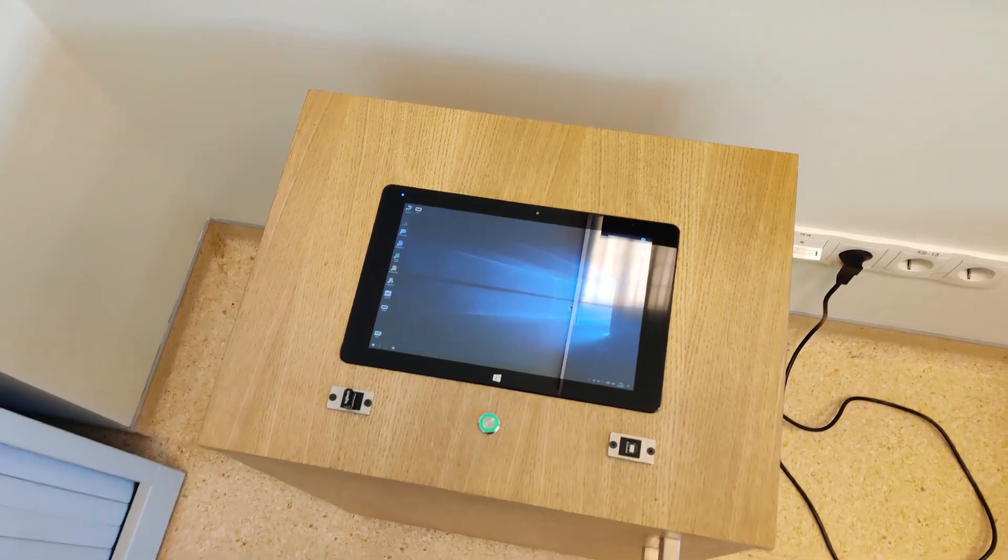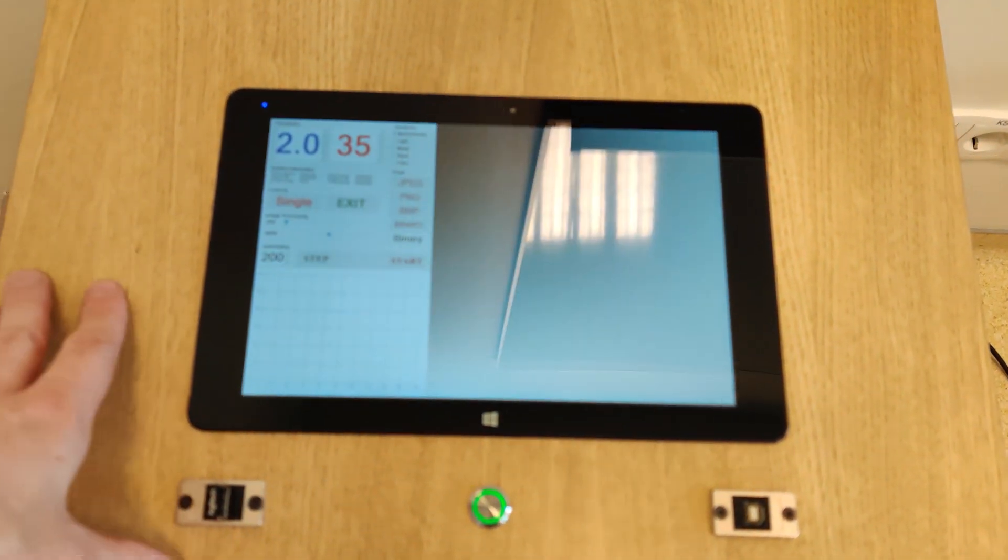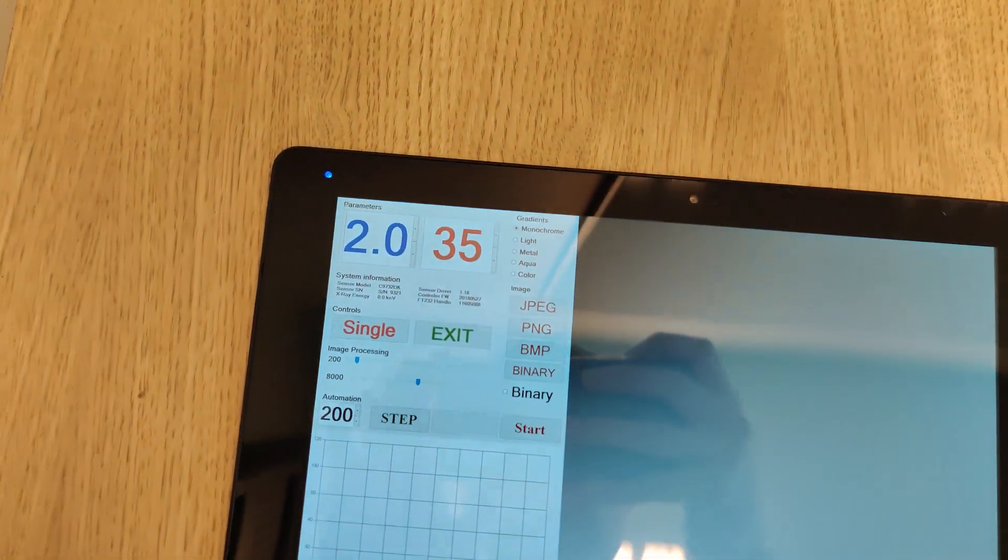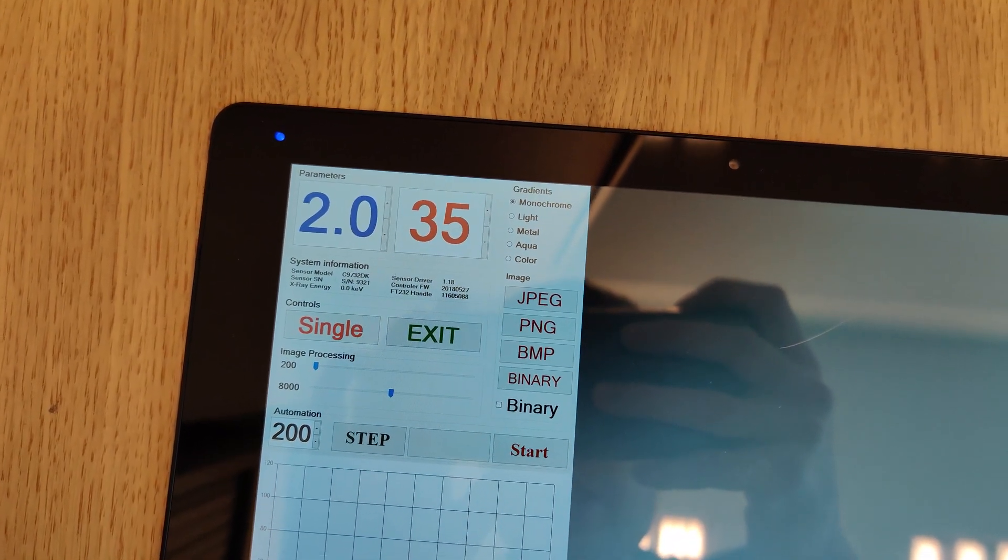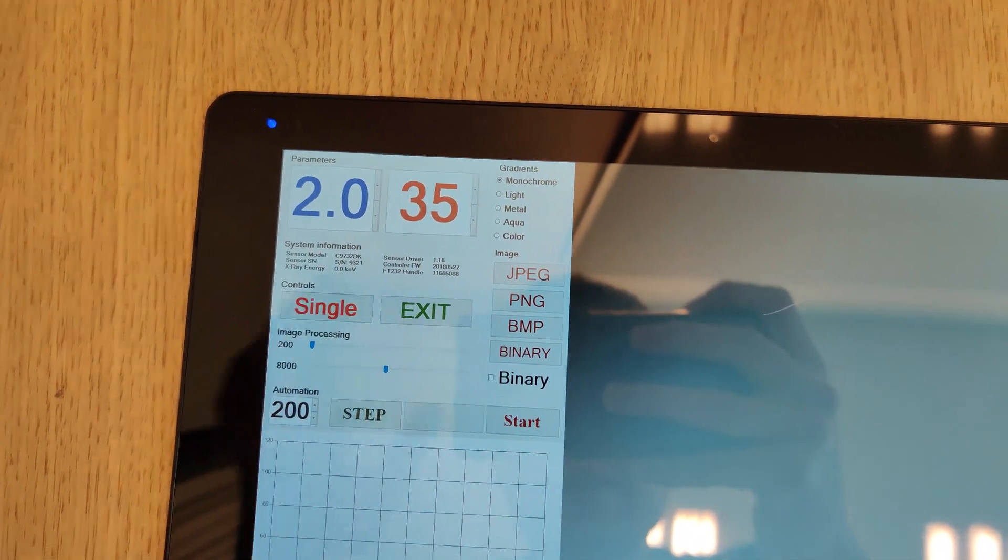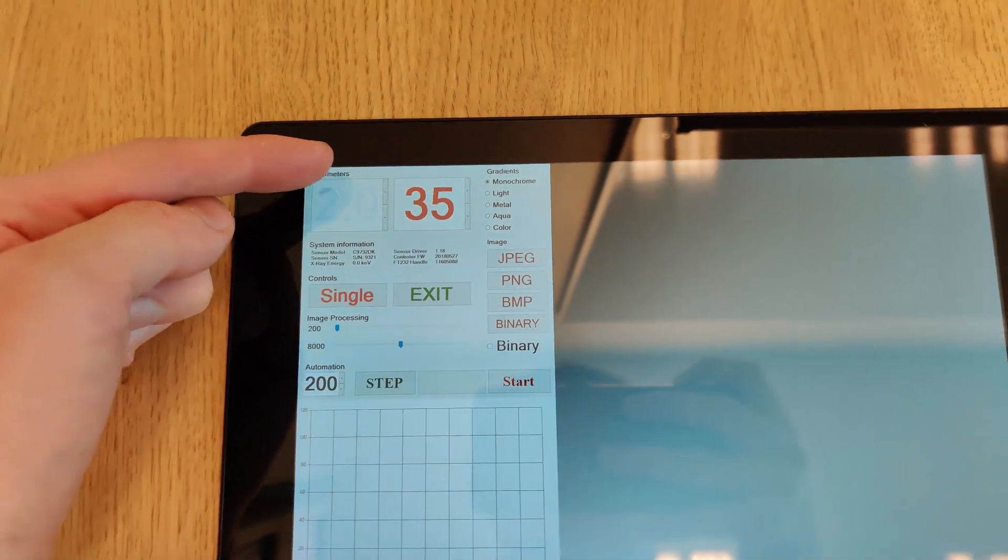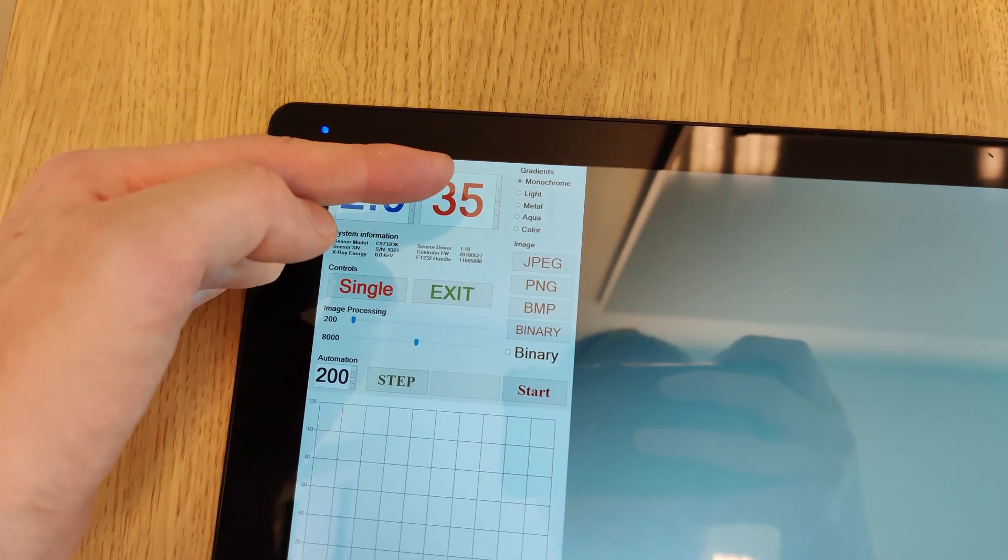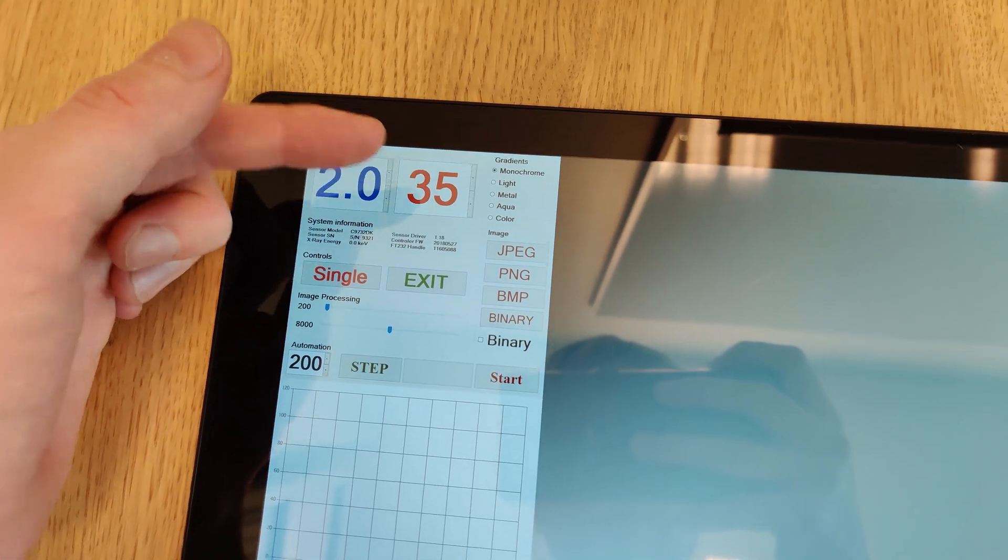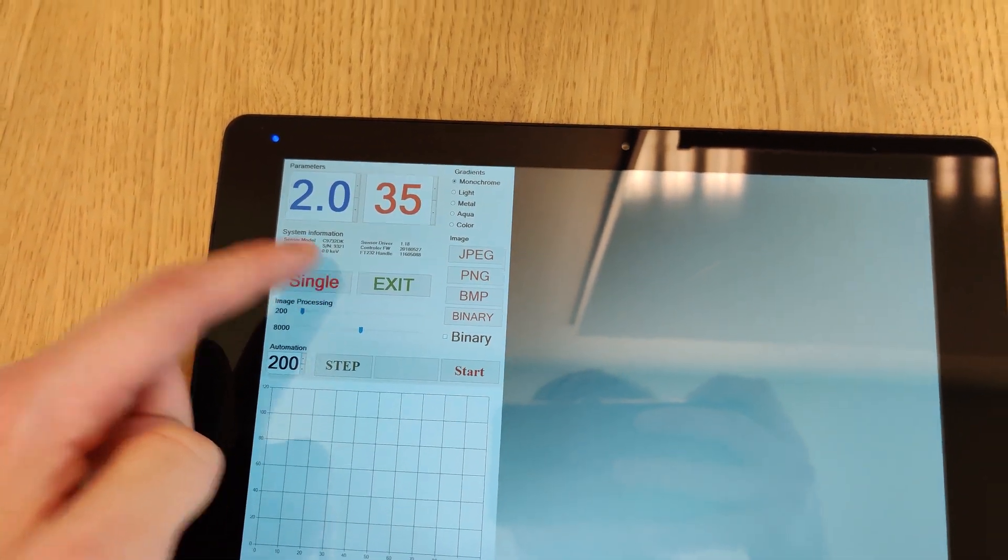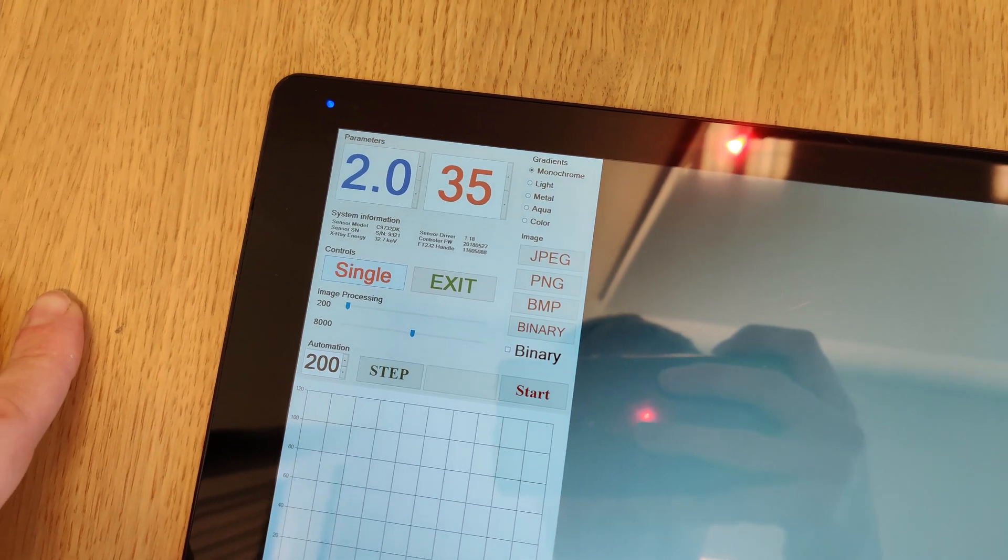Let's start the application - it's an x-ray scanner. It gives information about what sensor I have, what firmware I have, what's the PD handle, and what's the energy of the x-ray. This is the integration time and this is the energy, basically kiloelectron volts. Let's press single - as you can see, energy has ramping and I have an image.